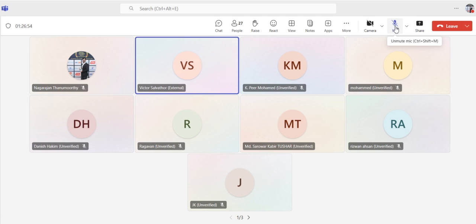Because the secondary pump is on the supply side, along with the return line. That's why I'm repeatedly saying this. The bypass line will come, but the suction side is there, right? The pump needs to suck the water from where? From the chiller side, right? There is a suction side for the secondary pump, so we have to consider that also, right?